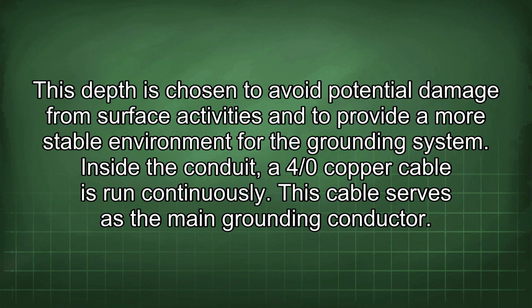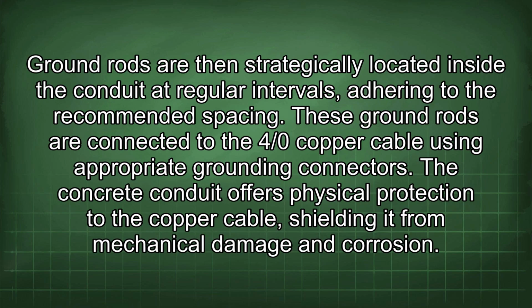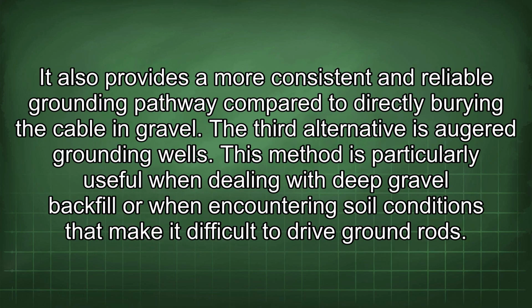This cable serves as the main grounding conductor. Ground rods are then strategically located inside the conduit at regular intervals, adhering to the recommended spacing. These ground rods are connected to the 4/0 copper cable using appropriate grounding connectors. The concrete conduit offers physical protection to the copper cable, shielding it from mechanical damage and corrosion. It also provides a more consistent and reliable grounding pathway compared to directly burying the cable in gravel.